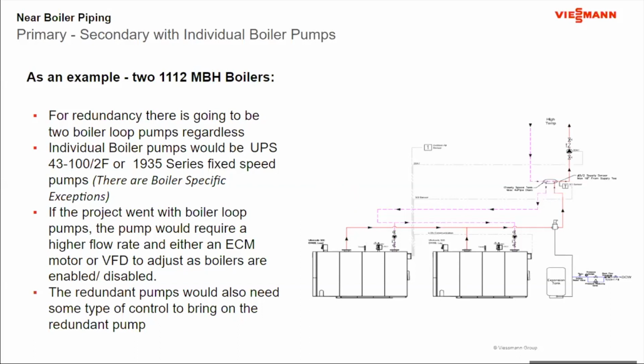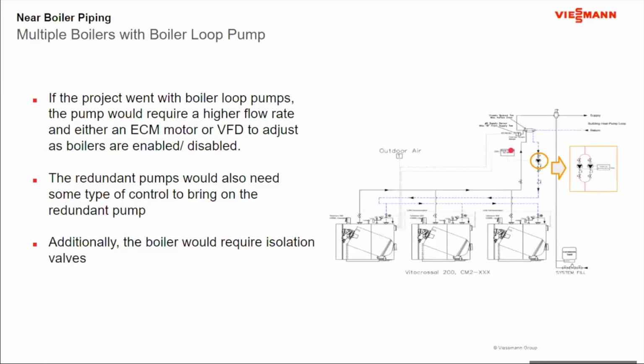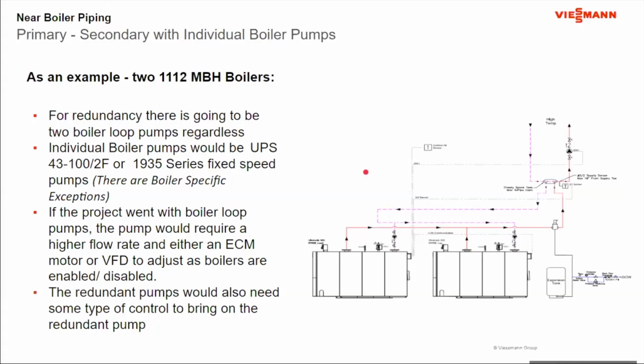From an option standpoint and what I see coming and going, I'd say I see more boiler pump systems like you see here than systems that have a secondary, a primary, a boiler loop pump, and then isolation valves on the individual boilers. This tends to be the way I see more projects going. Okay.